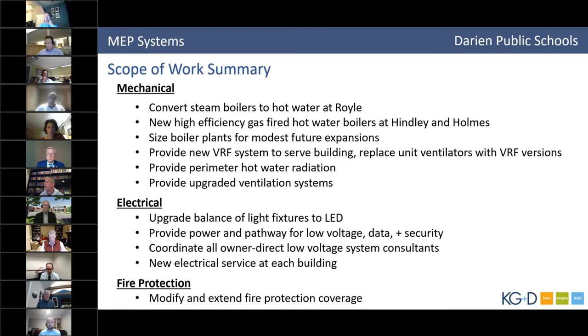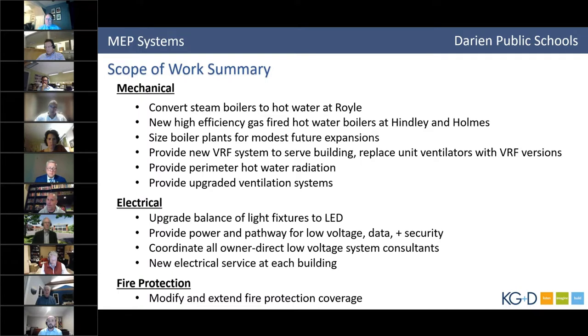Is it the primary source of heat? You've got a discussion on boilers which you'll address, but the primary heat source isn't the heat pumps, correct? We should go through the whole thing first since I'm addressing all that. You're going to have redundant systems - a heat pump system with cassettes and unit ventilators, and also hot water boilers, fin tube radiation, and hot water unit ventilators. So 100% redundant systems in every building. We're keeping the hot water you have and converting the steam you have - getting rid of your antiquated steam and converting it all to hot water. So you'll have 100% redundant systems, whether gas, oil in Royle's case, or electricity throughout.